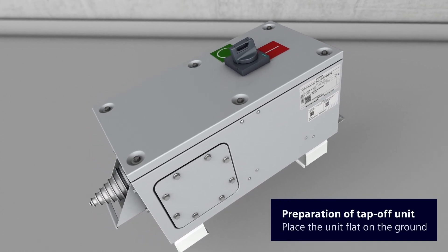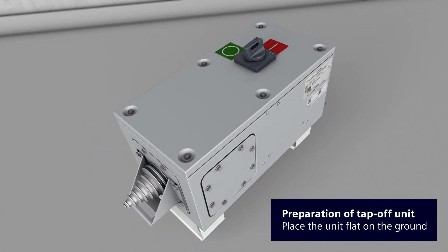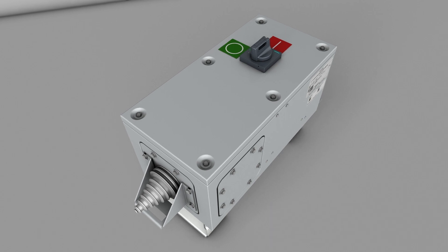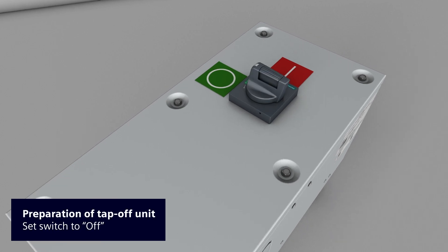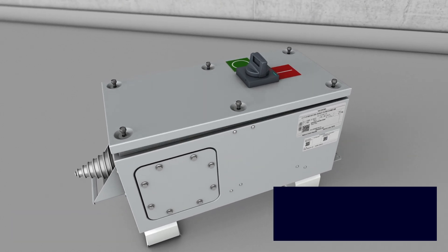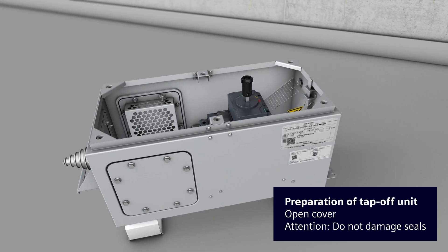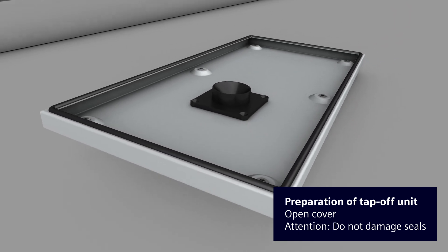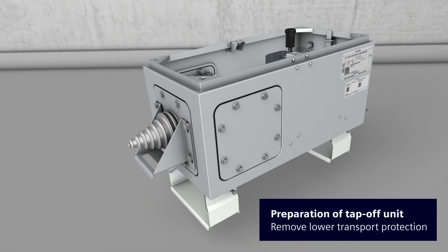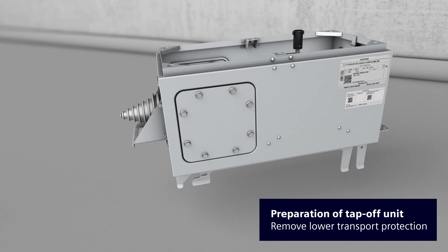Prepare the tap-off unit for installation. Place the tap-off unit flat on the ground. Set the switch position of the door-mounted rotary operator to OFF before removing the cover. Detach the cover screws and lift off the cover. Make sure not to damage the seals arranged on the inside of the cover. You can now remove the lower transport protection.